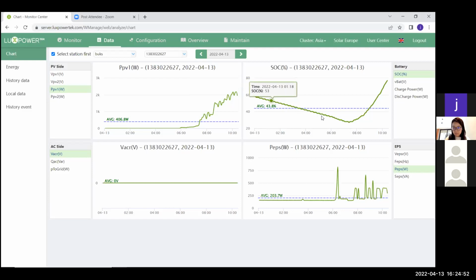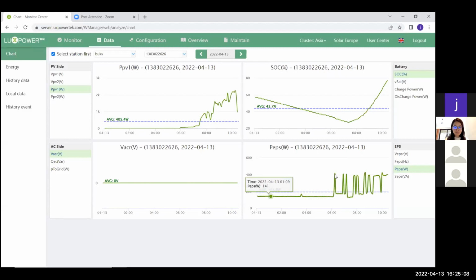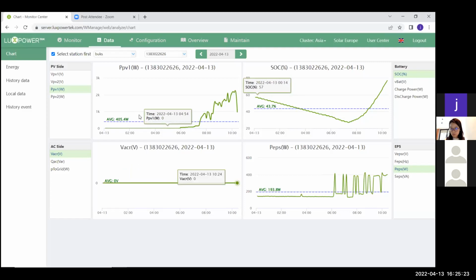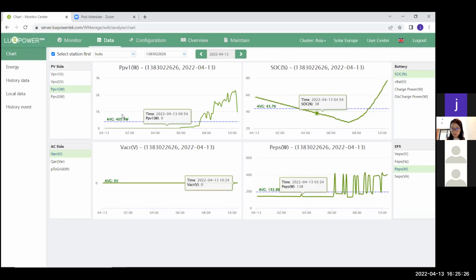State of charge, how the batteries were running down and charging up. What this inverter gave, 819 watts at this specific time. You can go to the other inverter and see that this one gave this amount of power at a given time. So you can basically track each inverter individually through all the days going backwards. I think the data is saved up to 100 days, if I'm not mistaken. That's useful if you want to troubleshoot your inverter, to see why your batteries are still flat, what is happening, and so forth.